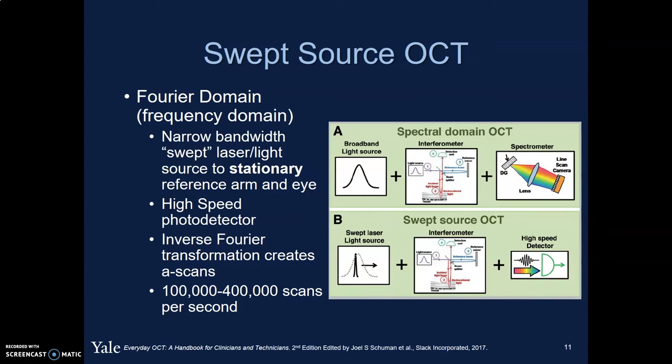Finally, there's swept source OCT. This is similar to spectral domain OCT in that it's frequency domain-based, but instead of using a broad bandwidth, it uses a narrow bandwidth laser that's sweeping back and forth rapidly to generate the interference. It requires a high-speed photodetector, making it a little more expensive. It uses an inverse Fourier transformation to generate the A-scans, and as a consequence it's faster, doing 100,000 to 400,000 scans per second.